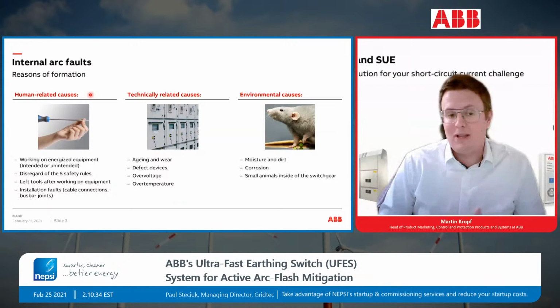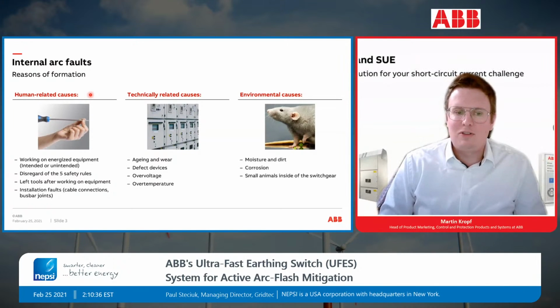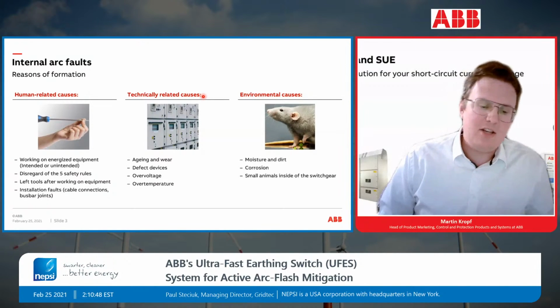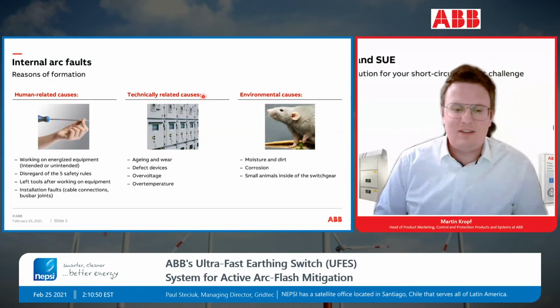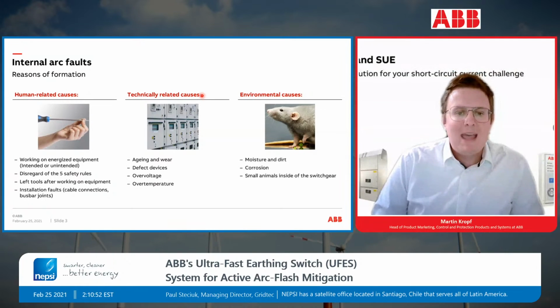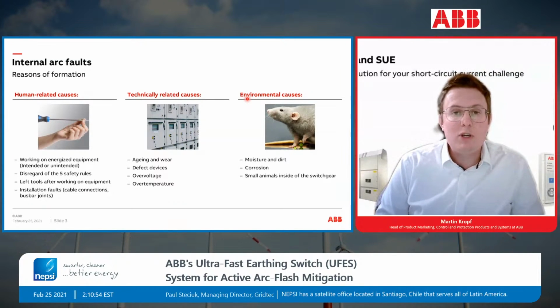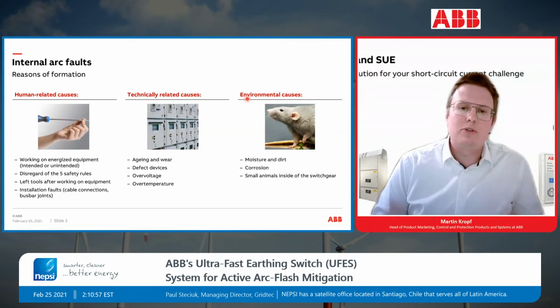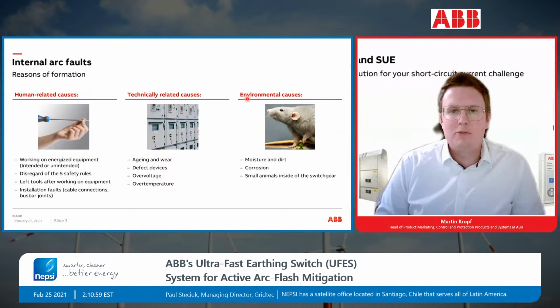And also what I would like to highlight: human-related causes also always mean that most of the time humans are close to switchboards, to the application, and this brings the safety issue as well. Then we have technical-related causes: aging, wear, defective devices, overvoltage, overtemperature, as well as environmental causes, so moisture, dirt, corrosion. We sometimes have animals in the switchboard, and these are all reasons which then cause an internal arc.